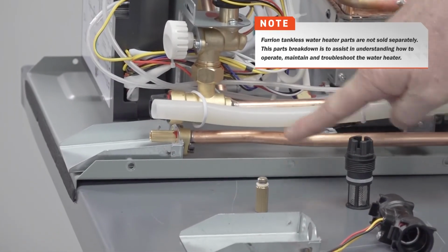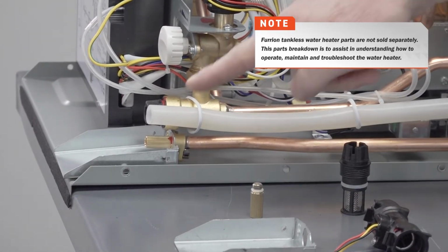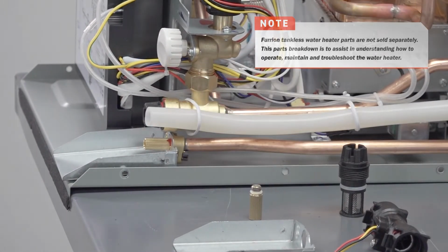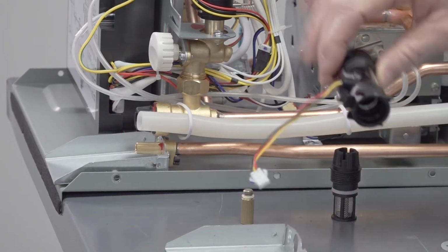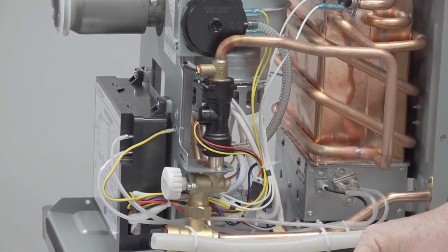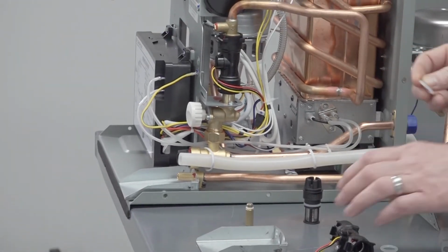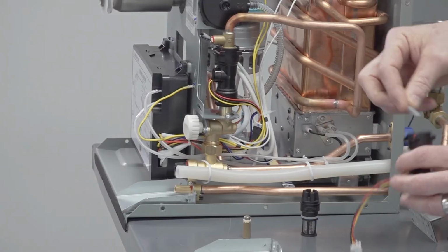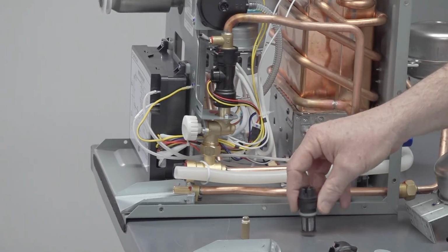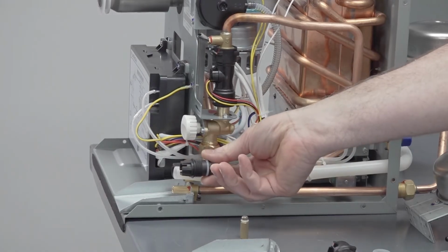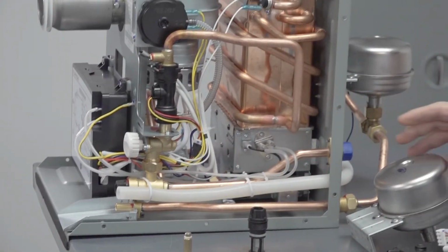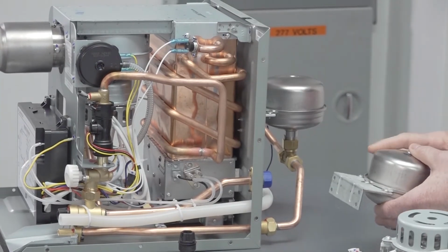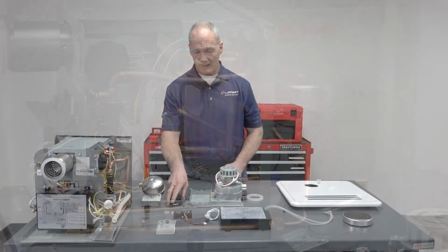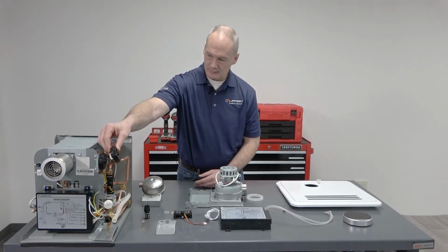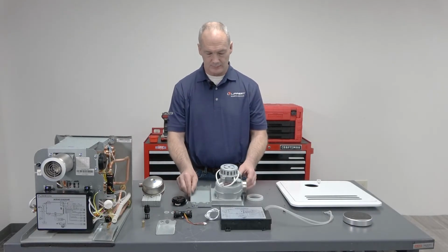Starting with the drain plug and the drain pipe. These are used for winterizing your unit, and the drain exit channel. Then you have your water flow sensor. It goes right here. And the O-rings that go inside the water flow sensor, and they connect to the copper tube. Then you have your water filter that we talked about earlier. Goes right in there. And your expansion tank that goes on the back of the unit. Next, we have our exhaust pressure switch. Goes right there. And the flue duct assembly.